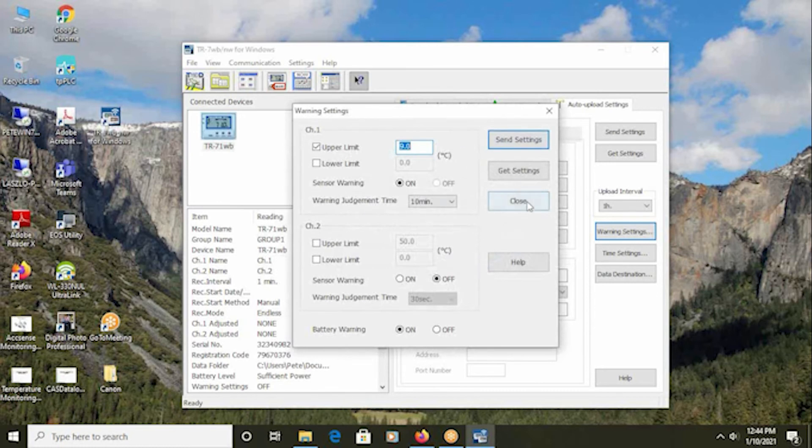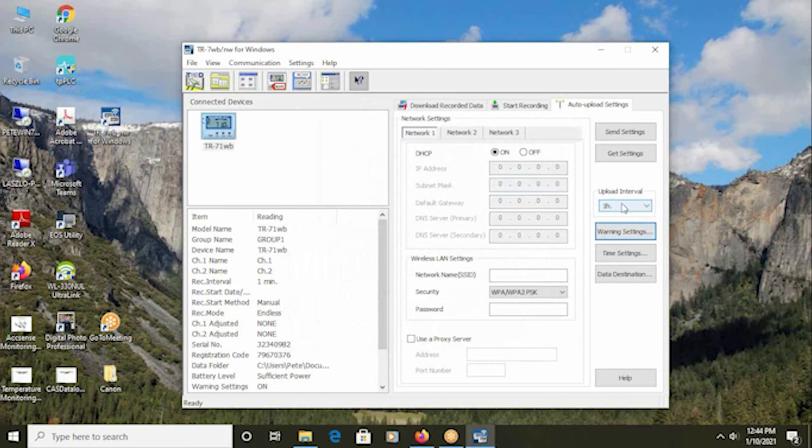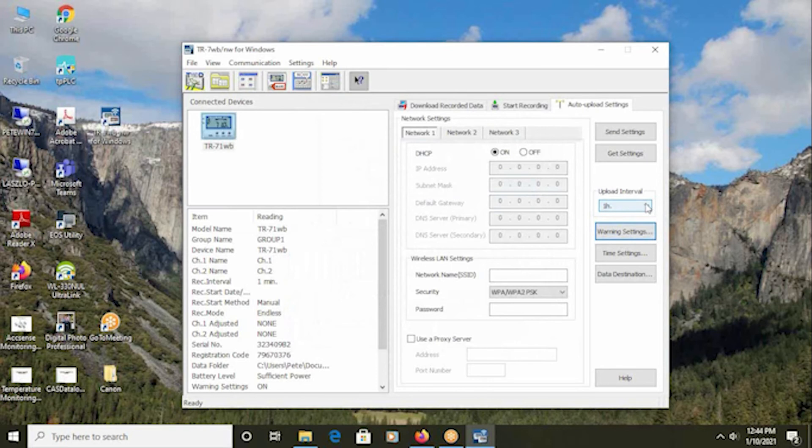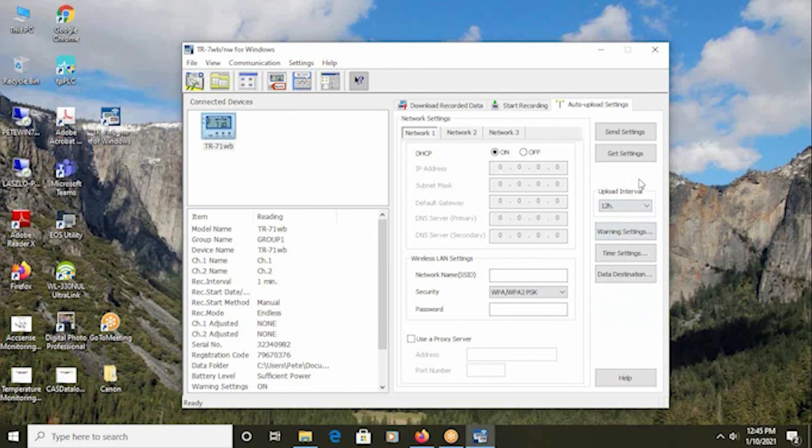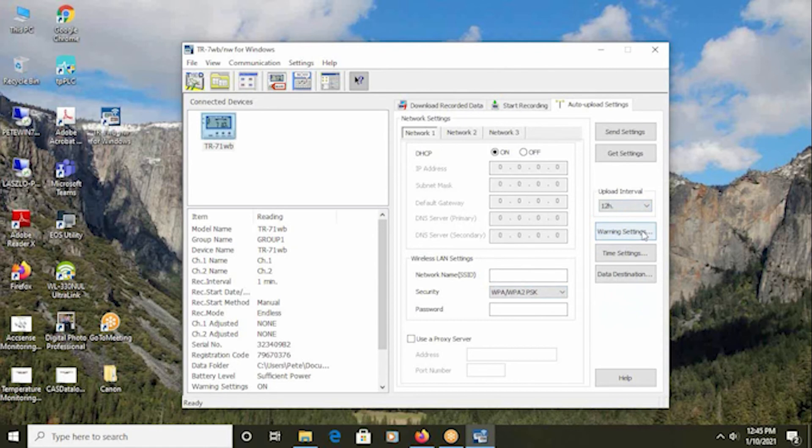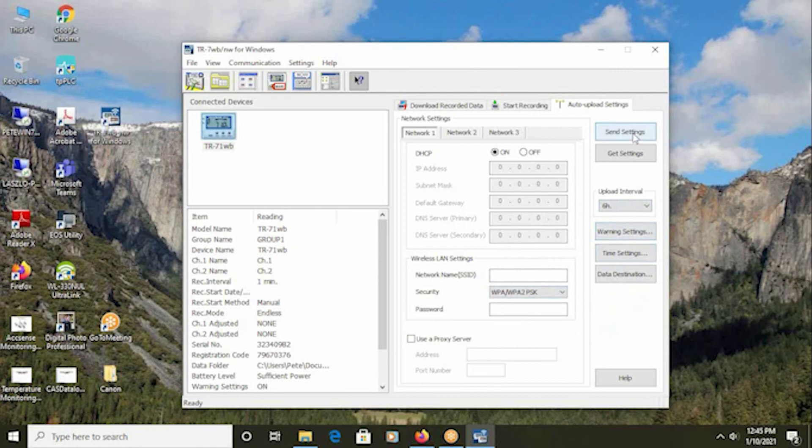The upload interval is how frequently will the logger take the collected readings in its local memory and push them up to the web storage service. This is the single most critical parameter that affects the battery lifetime of the logger. It should not be set too frequently, and it must be set at a longer interval than the record period. Once an hour is certainly appropriate, but every 12 hours may be good enough for the application. It's important to note that the alarming will be triggered strictly based on the judgment time, not based on this upload interval. The upload interval only speaks to how frequently will that data be pushed and available for viewing on the web storage service. Again, remember to send the settings.